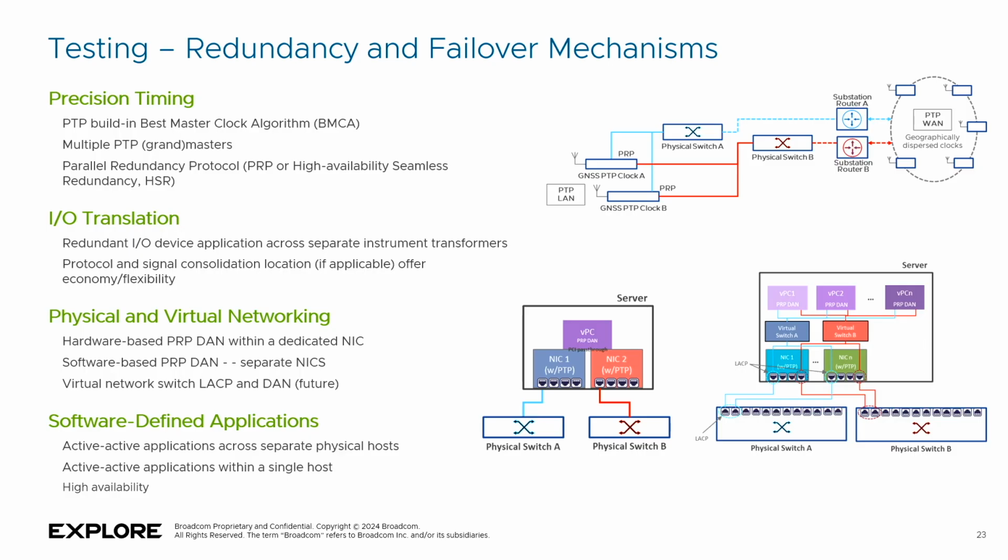But we have been failing over links, failing over equipment, making sure that the seamless redundancy, redundancy with no downtime, is intact. I/O translation redundancy. So instrument transformers, we're very used to having redundancy in that, but protocol conversion, this would be the protocol type in the I/O translation comes down to the merging unit.